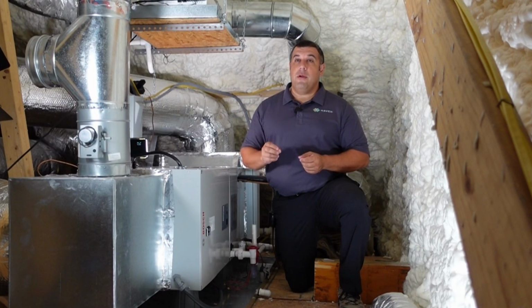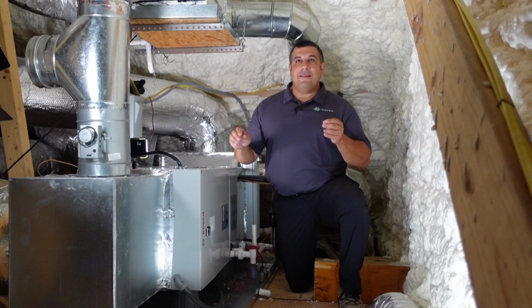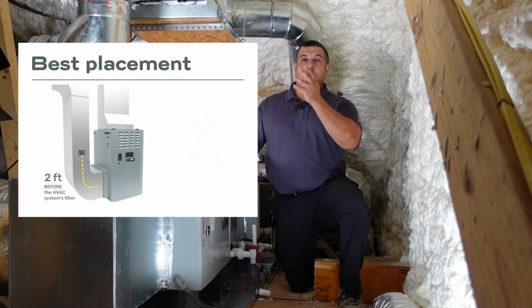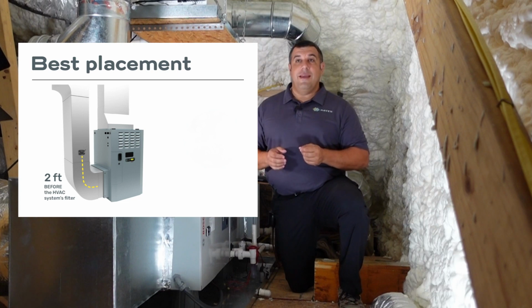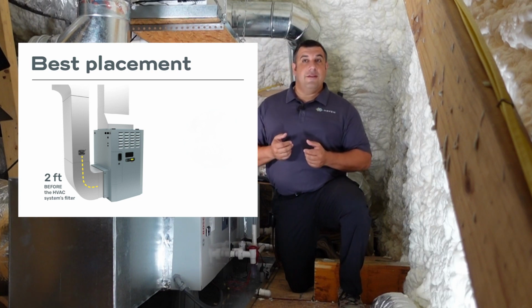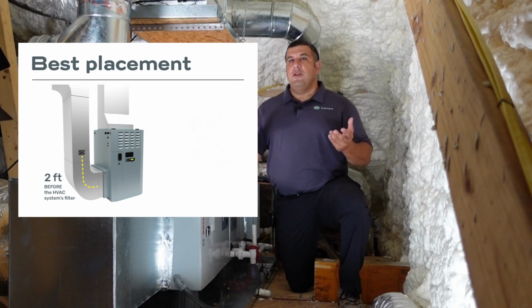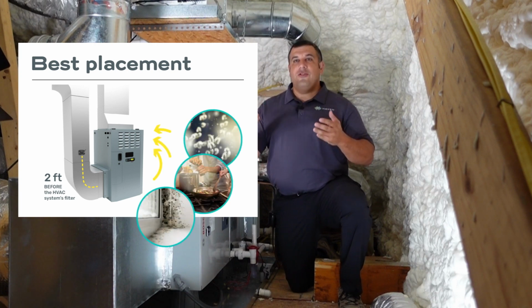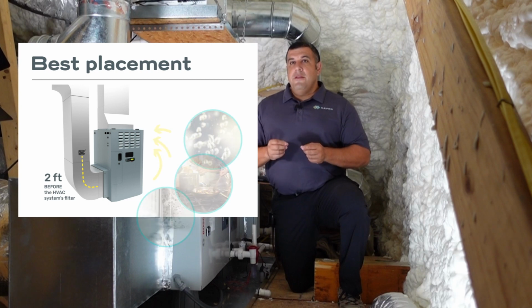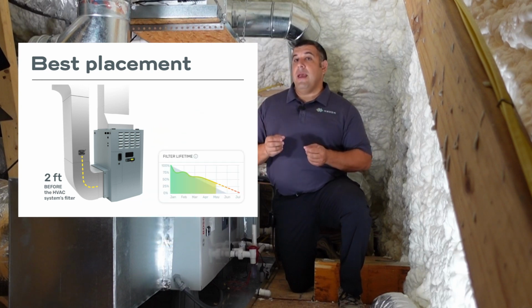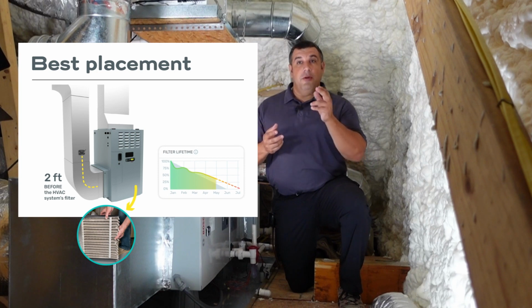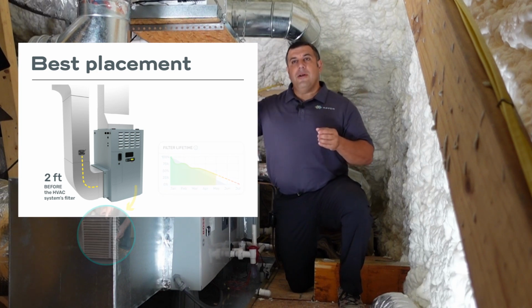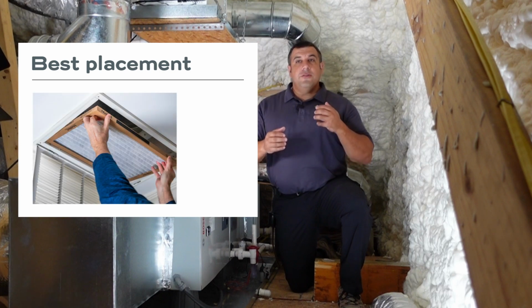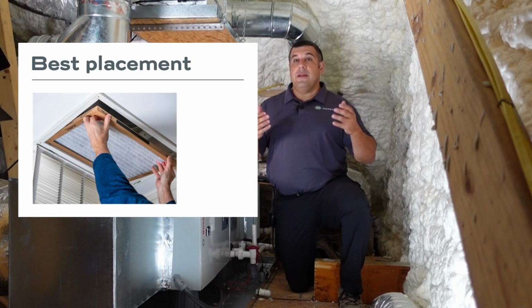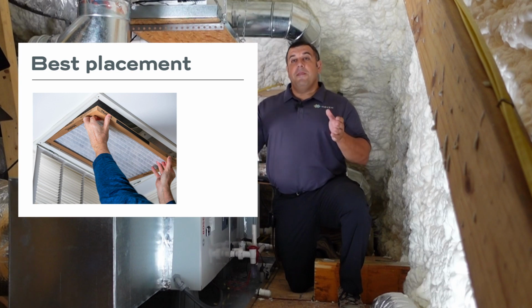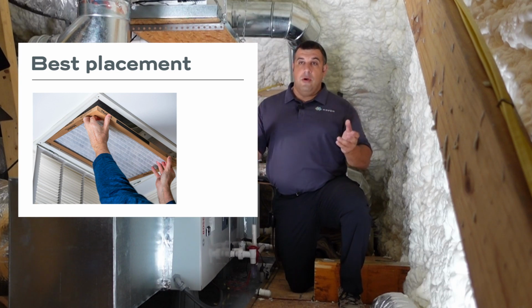Now we'll run through some important information on duct placement. The best place to install the monitor is in the return ductwork before the filter of an HVAC system or any other HVAC accessory, essentially where the air is going to be the dirtiest, so it can tell what action is needed from the sensor readings. This also ensures accurate filter lifetime calculations and replacement predictions to both you and the homeowner. If installed after the filter grill, for example, you'll still be able to see how well the filter is doing at removing particles from the home, but the filter lifetime calculations will no longer be accurate.